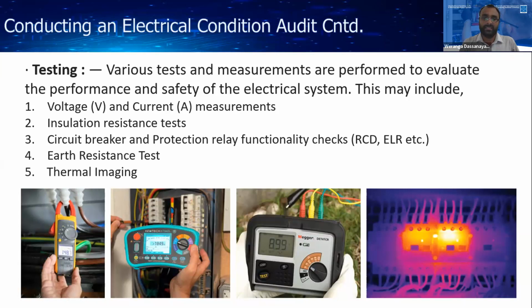Like that, you can check. Then earth resistance test. That means checking that the main earth or the lightning protection system earth are earthed properly and have met the required resistance level. Then you can use a thermal imaging camera to detect the heated point or power loss point.